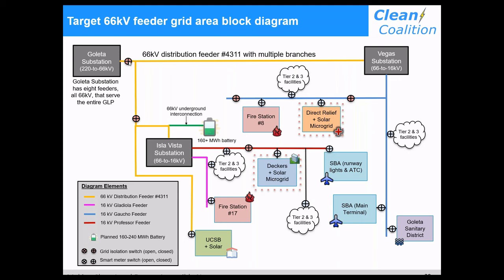There are 8 66 kV feeders that come out of the Goleta substation, but this switch will allow us to isolate this particular 66 kV distribution feeder, which is referred to as number 4311, from the other 7 66 kV distribution feeders. And we do that to make sure that we have enough energy to keep our tier 1s and tier 2 loads within this footprint online, right? The tier 1s have to be maintained indefinitely.